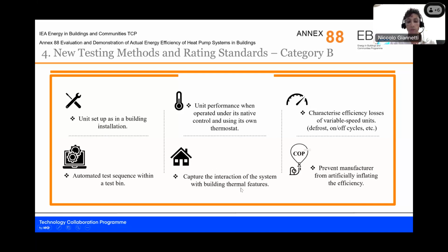Then it should be able to capture the interaction of the system performance with the building thermal features, so the thermal inertia of a room where it's installed. And these automated tests, operating the system as it would be operating in the field, also prevent some, let's say, procedure that could artificially inflate the efficiency of the system during the test.